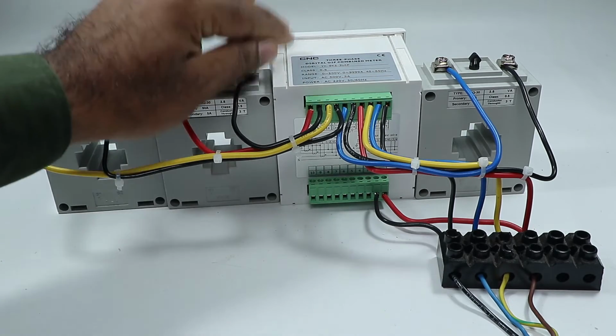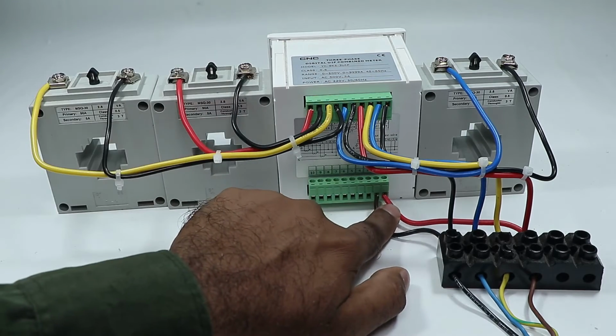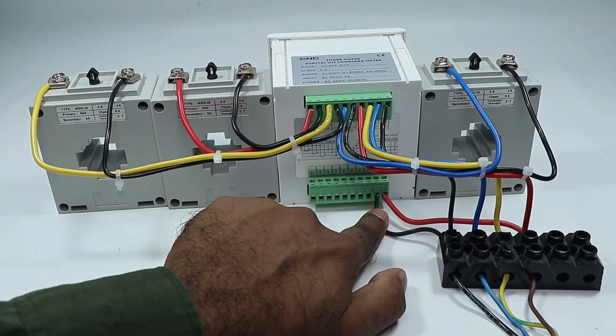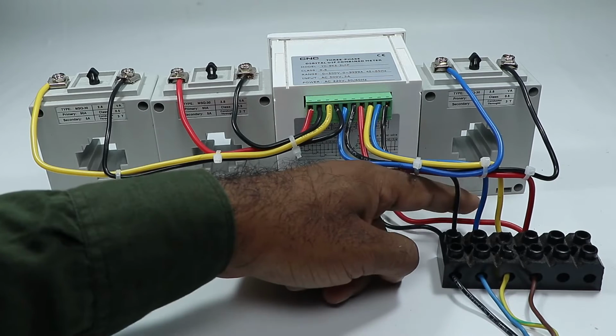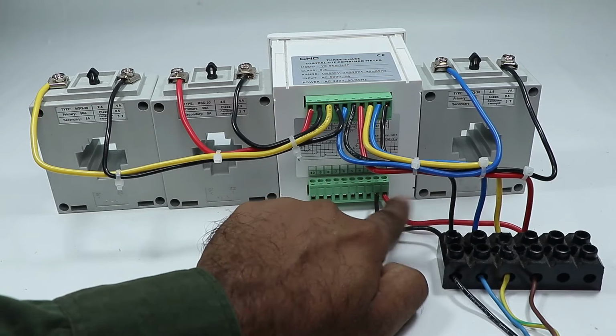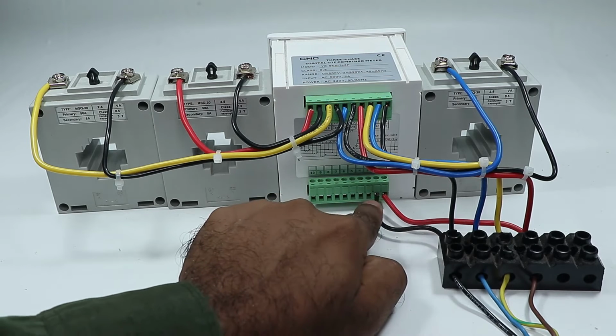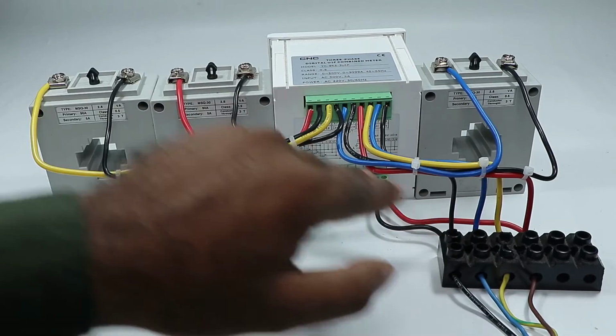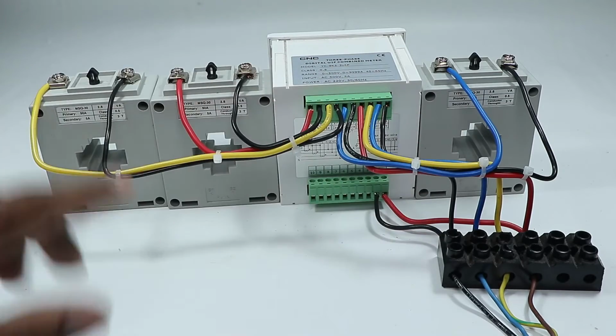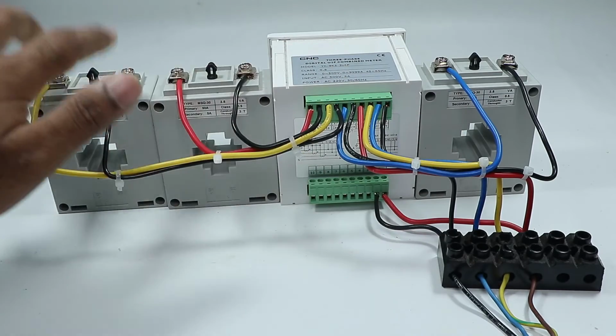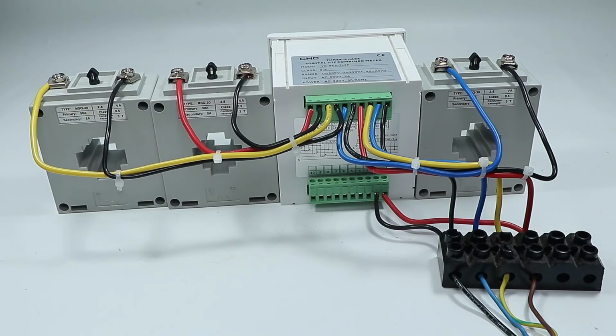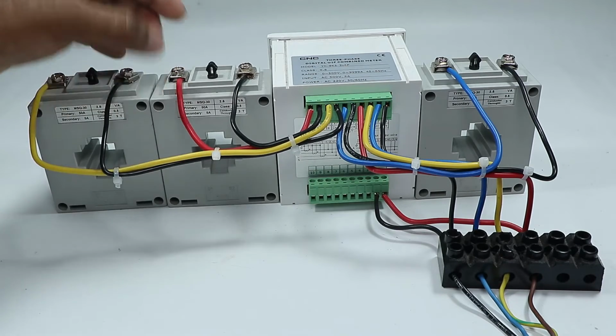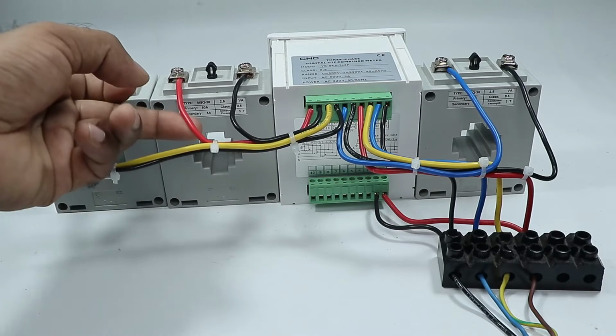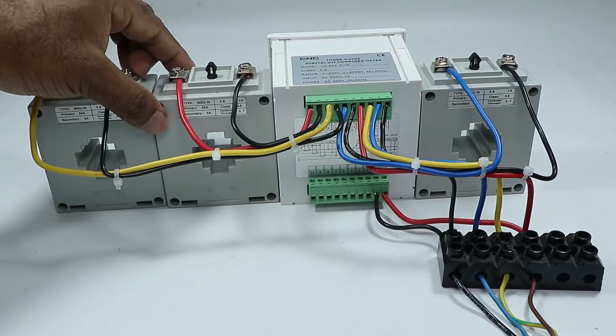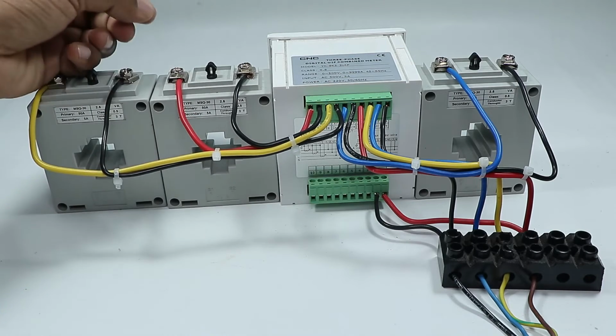For providing auxiliary power supply, below here you will find terminals 1 and 2. You can see I connected this red wire at terminal 1 and this black wire at terminal 2. After this, the CTs we have each have 2 terminals, and with all these 3 CTs I connected 2 wires. In this current transformer I connected the red wire, meaning this CT will be used to measure the R phase power supply.